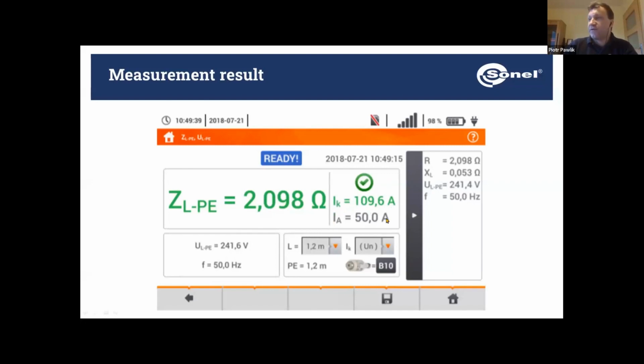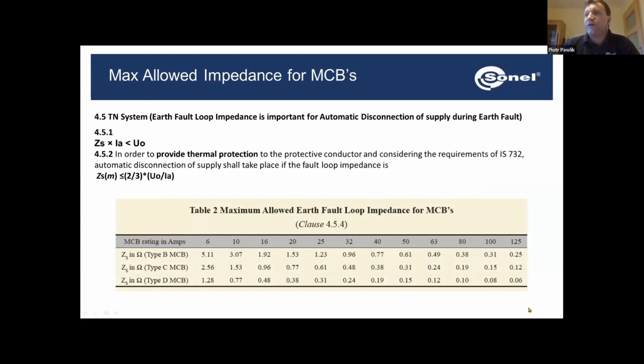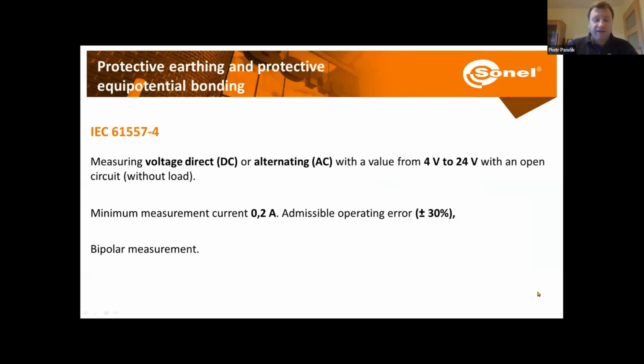And obviously, fault current is higher than the current triggering our breaker. That's why the meter has evaluated the result as positive. That's why we can see green check over here and the results in green. In case of a negative evaluation, we would see all these values in red. Okay, now further on, in case we would like to provide thermal protection in a three-phase network, then for these calculations, we need to use the 2/3 of the measured fault loop impedance. Okay, so that was a protection in case of a fault.